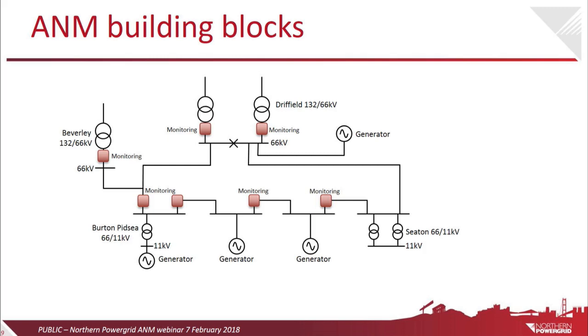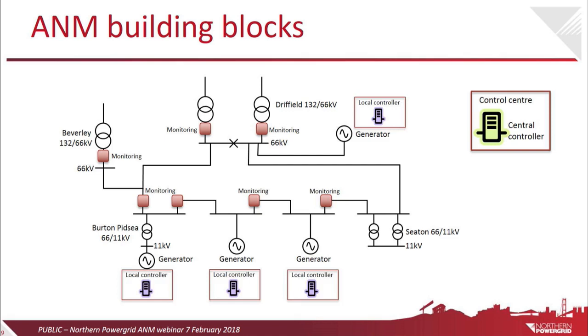In order to keep these constraints in check by keeping power flows within plant capabilities, we'll need some additional network monitoring at key locations, which has just popped up on screen now. We'll also need a central controller that will be located at our Yorkshire Control Centre that will use the monitoring data in real time in its analysis. So this is effectively the brains of the ANM scheme, if you like, and it uses this network data in its real-time calculations to control what the generators can export at any one time during the day and throughout the year. There will also be some local controllers at the generator sites, and these will monitor the generator export and their behaviour and pass on the instructions that they receive from the central coordinating controller back at our control centre. So the brain, if you like, at Gelderd Road is telling the local controllers what the generators can and can't do, and the local controllers pass that information to the generator.